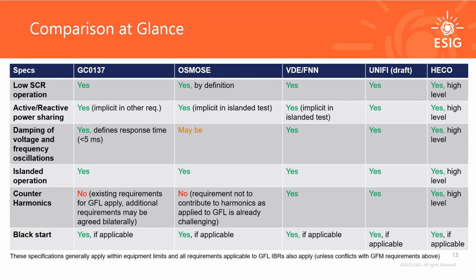And again, low short circuit strength operation is everywhere. Active reactive power sharing is either implicitly called upon, or if you're reading through island operation and how it is defined, you understand that active reactive power sharing is required there. Damping in the OSMOSE report is there because the French system operator already requires damping from grid following inverters. So they say that maybe additional damping capabilities may be required from grid forming, but they haven't quite defined it. And then countering harmonics is not defined in the GB requirement, and in OSMOSE it isn't because both of them recognize that it's already required from grid following, and they need to investigate if additional capabilities are needed there.